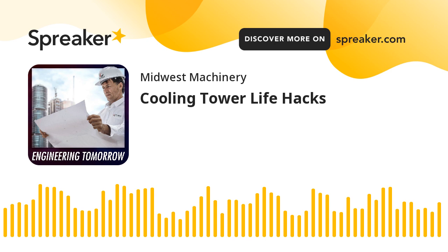When you look at gear drive versus belt drive: for belt drive, you're going to be tightening your belts several times a year and replacing them probably at least once a year, just a lot more getting into the tower and putting your hands on the drive system. With a gear drive, you're really only checking oil and eventually changing oil. I'll talk in a minute about how frequently you have to change the oil, but checking oil is very simple compared to tightening and replacing belts. Another big advantage of gear drive versus belt drive is energy transfer.